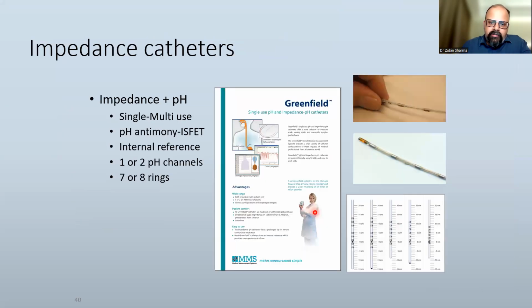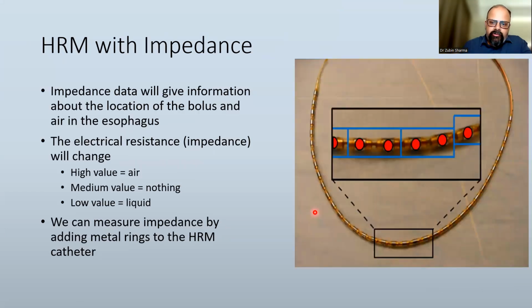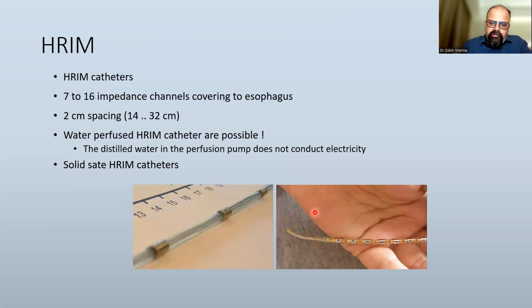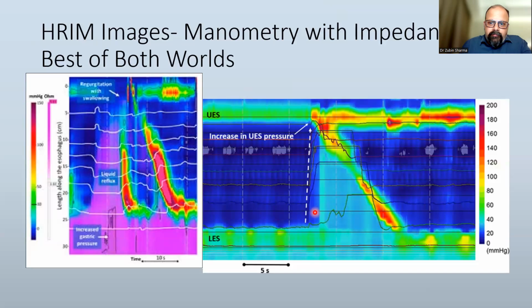If I just have to go ahead, I think this is the other common impedance manufacturer catheters that are available. They are antimony based. They have an internal reference, and finally, we have to standardize them. You can also combine HRM with impedance. The impedance data will give information about the location of the bolus and the air in the esophagus, and we can actually measure using metal rings on a manometry catheter. So this is how it looks to combine a manometry catheter with an impedance channel. This is how it looks when you combine on the software itself.